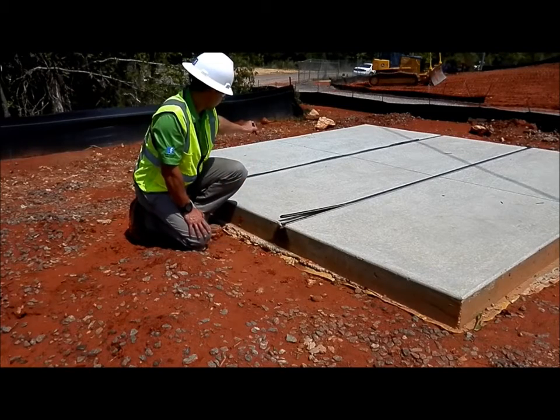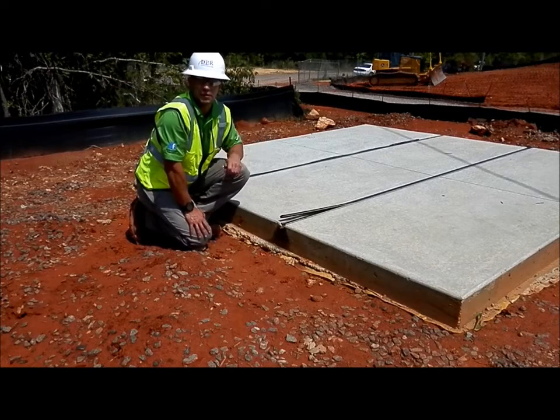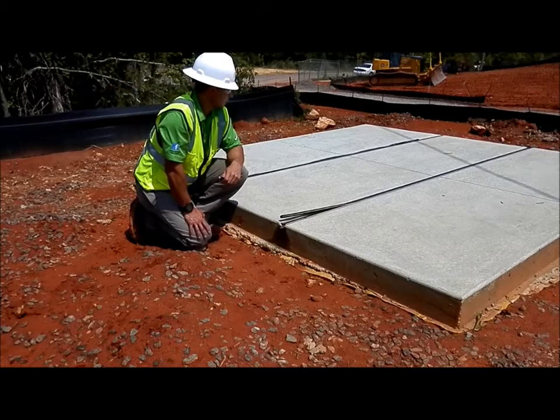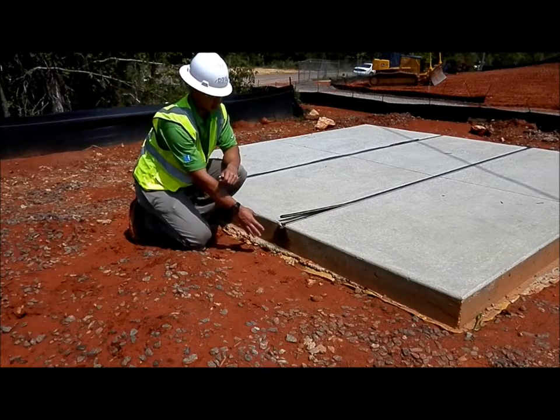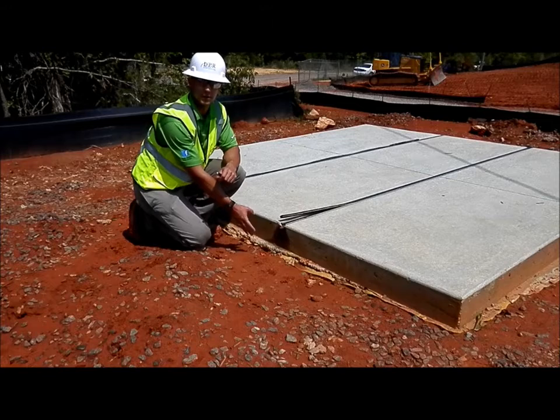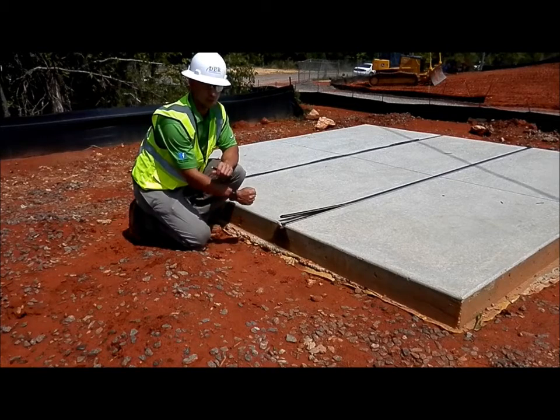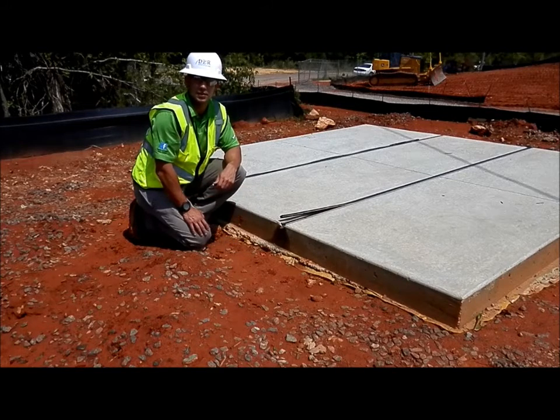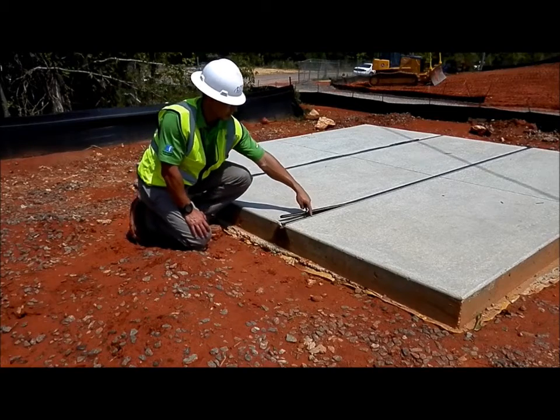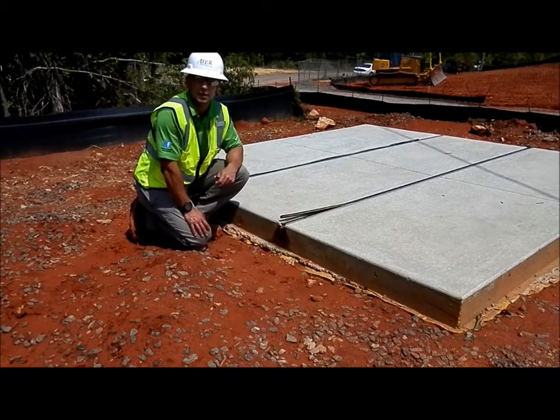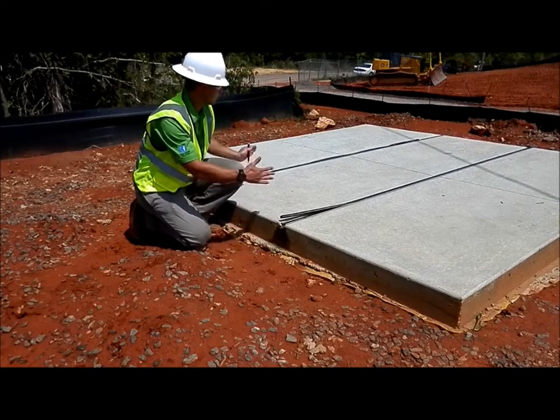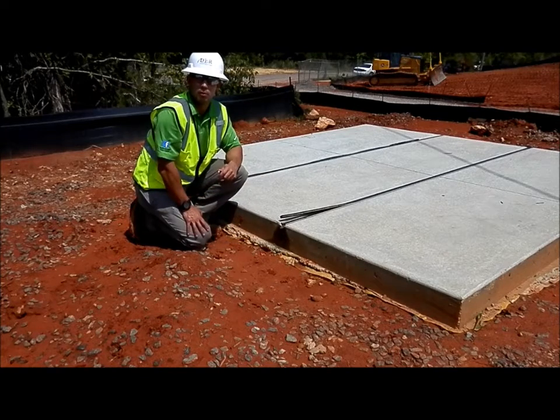It's very critical that these unistruts are exactly 3 feet apart, so to minimize that risk we poured a 4-inch mud slab underneath this into the subgrade and drilled threaded anchor rods into the mud slab, then tack welded them to the edges of the unistrut to minimize any risk that we wouldn't be exactly parallel when we pour this slab.